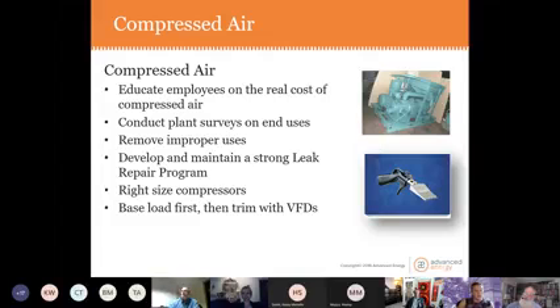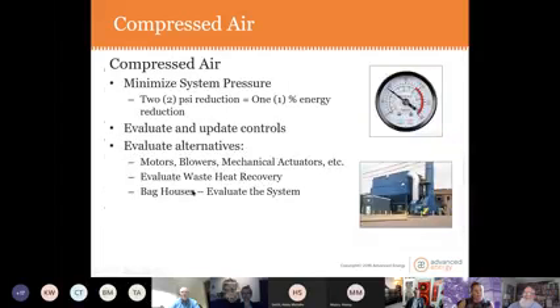A trim compressor with a VFD can float that, and you base load just a regular compressor without a VFD, and that's a very efficient way to do that. Nozzles, they make very efficient air nozzles that use the minimum amount of air for blowing air. Every plant I see, you see people blowing down dust or cleaning or using air hoses for all types of stuff. Minimize the system pressure. Don't operate the plant at 150 psi if you can run it at 120 psi.